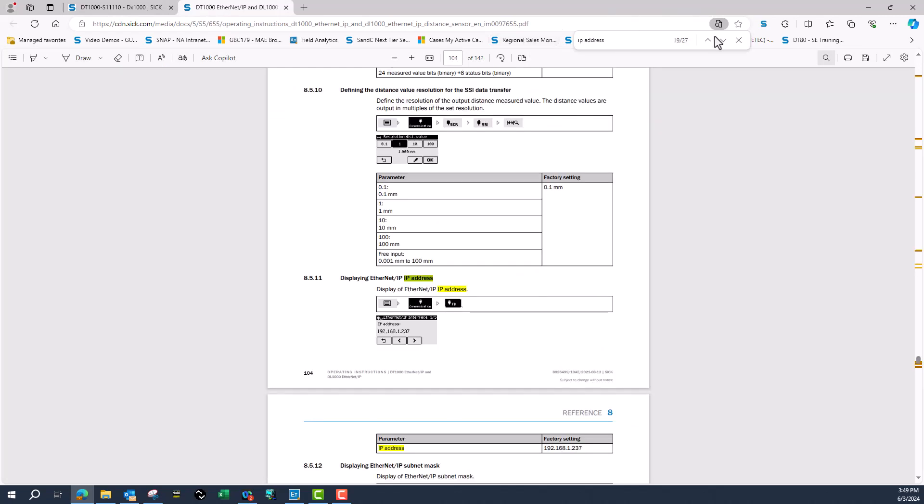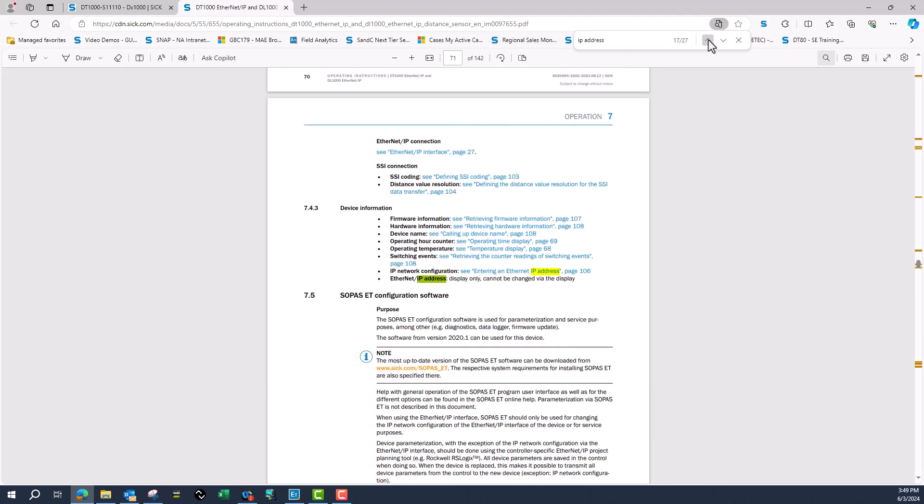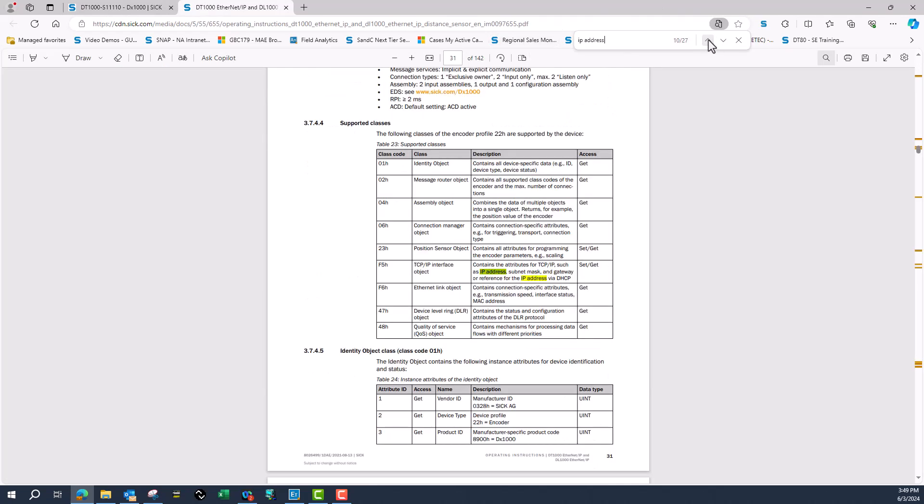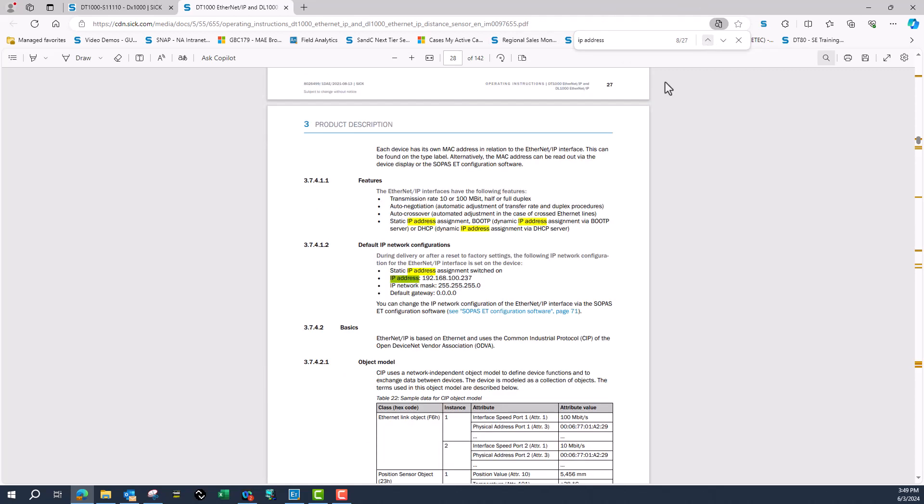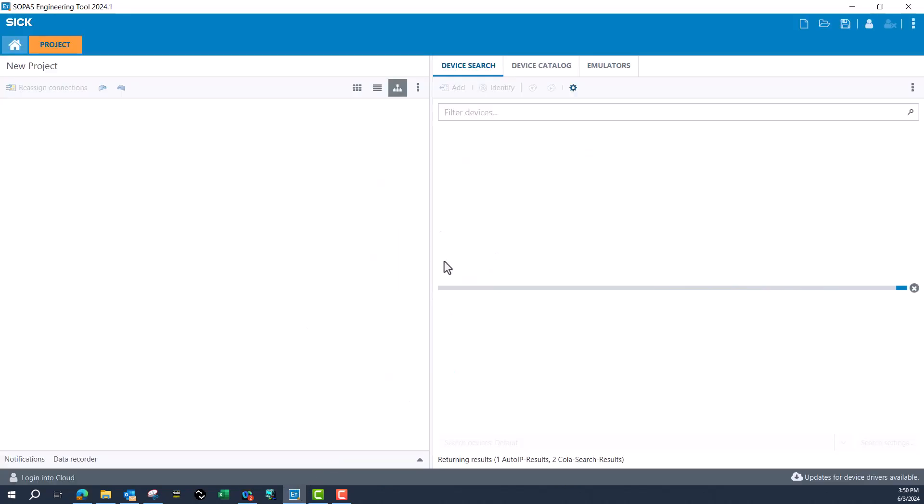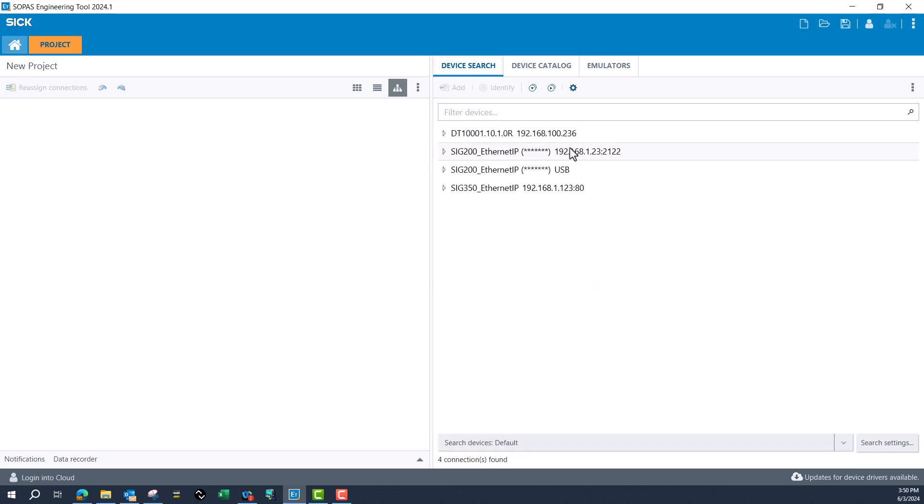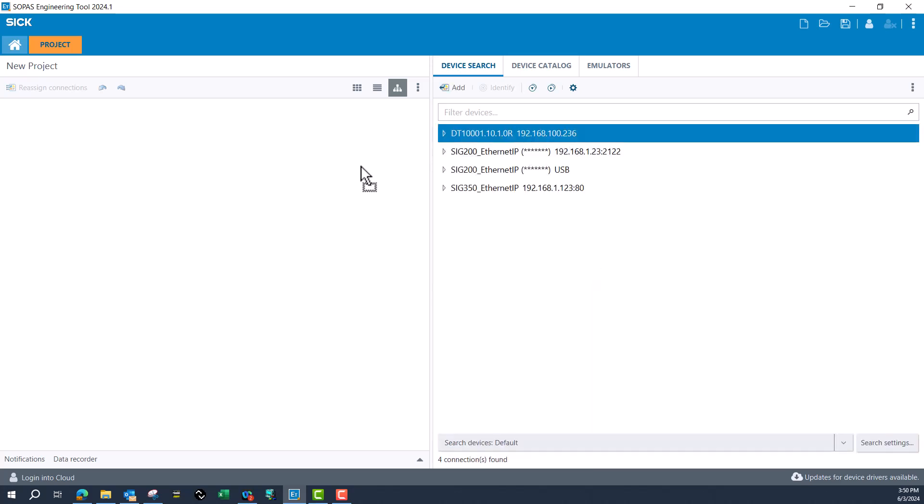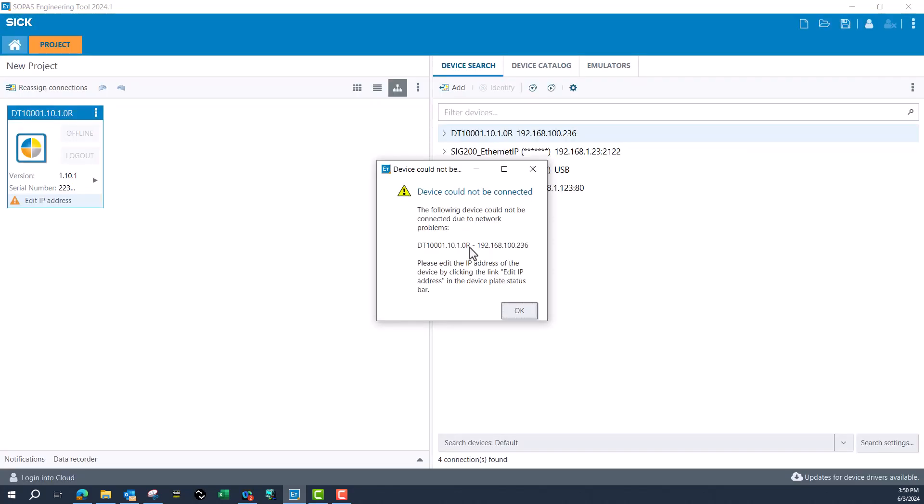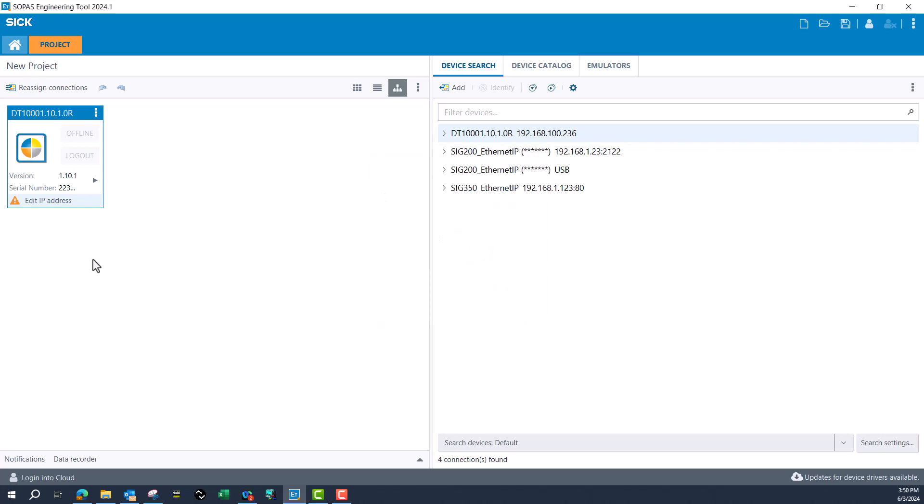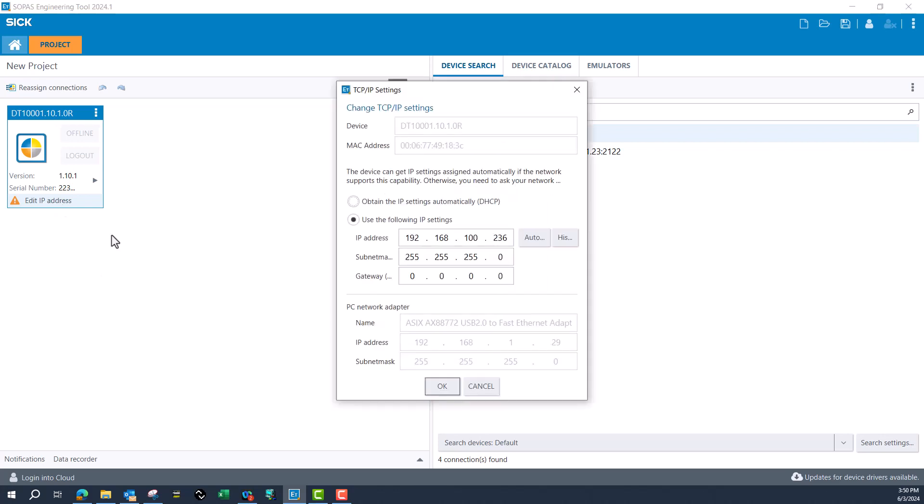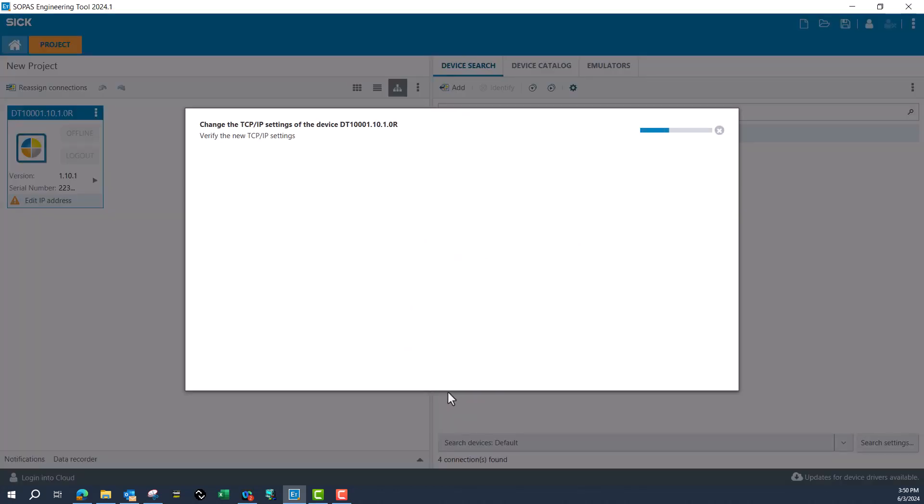The default IP address of the sensor is going to be 192.168.100.237. My computer is 192.168.1.29. I'll go ahead and let SOPAS reach out and find the sensor, then go into the sensor and change the IP address. I don't have to change it on my computer. I can go auto, change that third octet, and let it find itself.